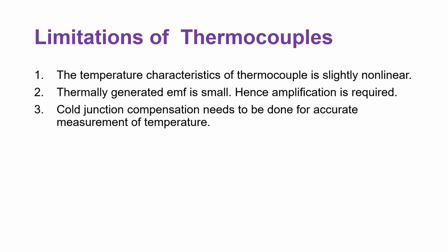Then second, the thermally generated EMF is small, so amplification is required. If you are going to use a thermocouple in any application, then the output of the thermocouple should be applied to an amplifier for amplification. Then the third limitation: cold junction compensation needs to be done for accurate measurement of temperature.